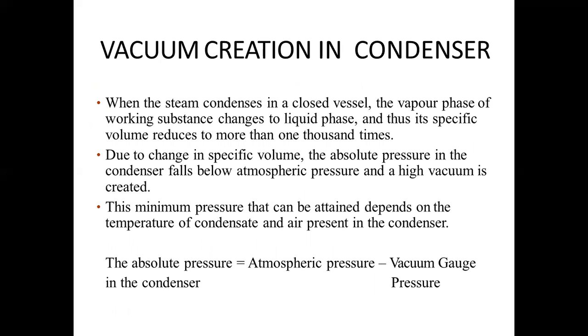Now, vacuum creation in the condenser. When the steam condenses in a closed vessel, the vapor phase of the working substance changes to liquid phase. Thus, its specific volume is reduced to more than 1000 times. Due to the change in specific volume, the absolute pressure in the condenser falls below atmospheric pressure, and a high vacuum is created. The minimum pressure that can be attained depends on the temperature of the condensate and the air present in the condenser.